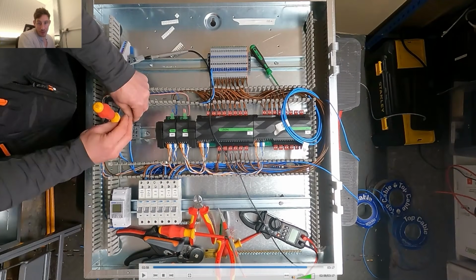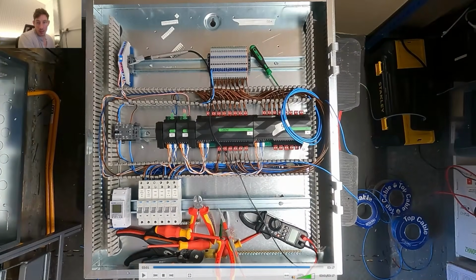Here I'm just wiring in the control side, A1, A2, because a contactor is ultimately a relay. So we're wiring the control side, A1, A2, coming from a relay extension, and then we've got the supply on here coming from an RCBO and going out here.